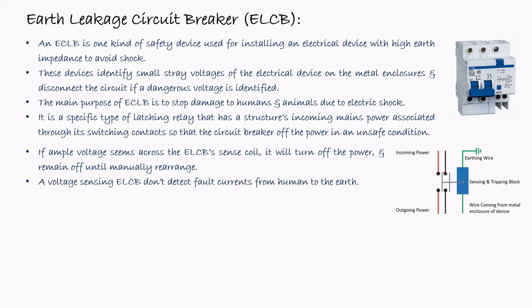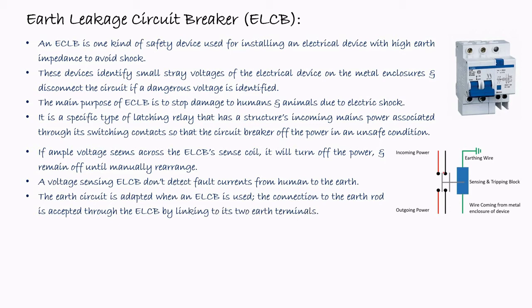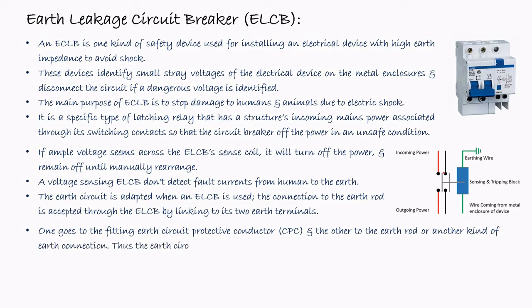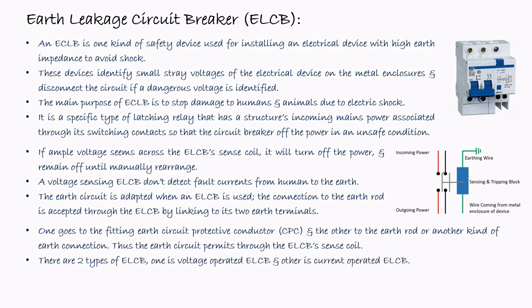If a voltage sensing ELCB doesn't detect the fault current from human to the earth, the earth circuit is adopted when an ELCB is used. The connection to the earth rod is made through the ELCB by linking to its two earth terminals. One goes to the fitting's earth circuit protective conductor, that is CPC, and the other to the earth rod or another kind of earth connection. Thus, the earth circuit passes through the ELCB's sense coil. Basically, there are two types of ELCB. One is the voltage operated ELCB and the other is called the current operated ELCB.